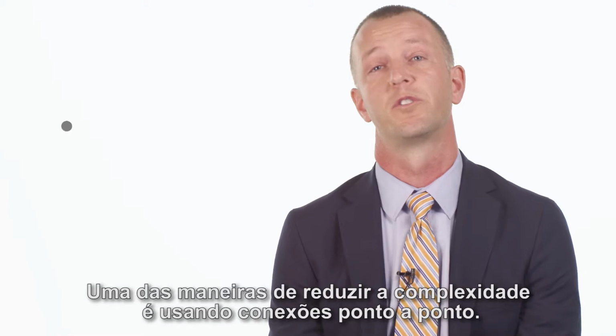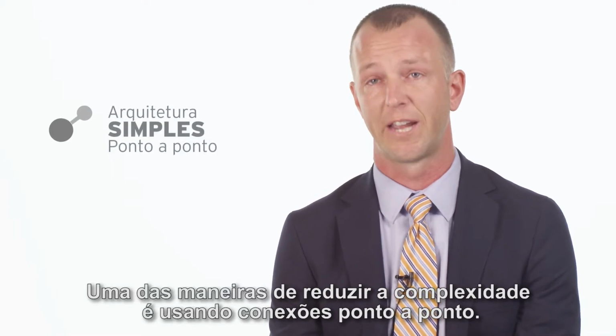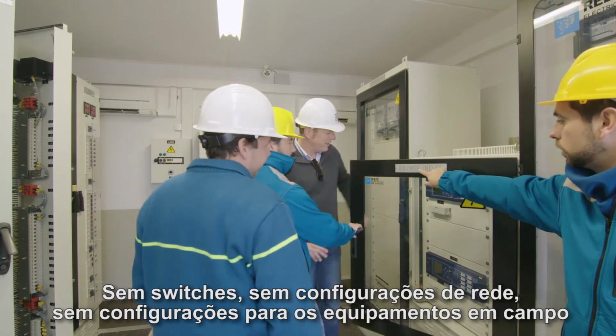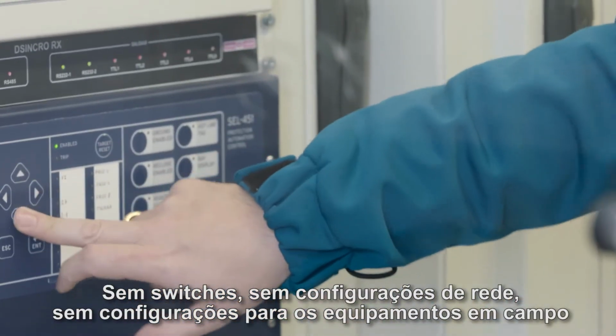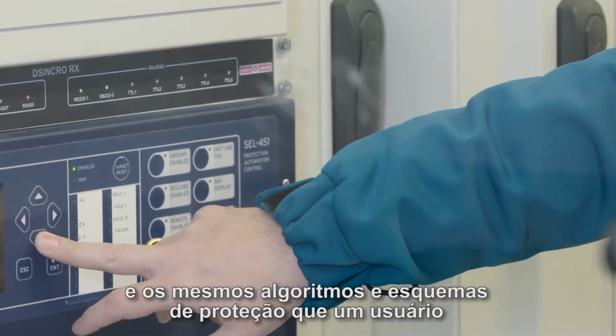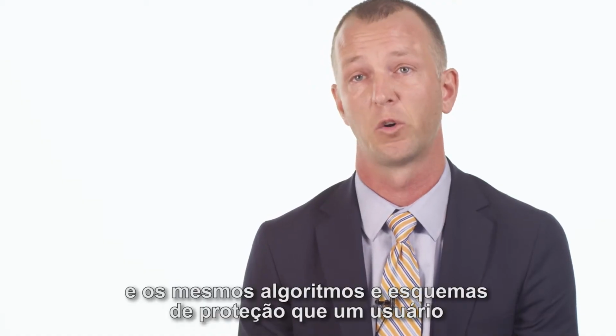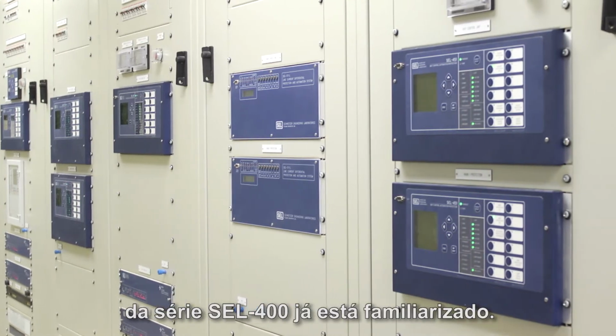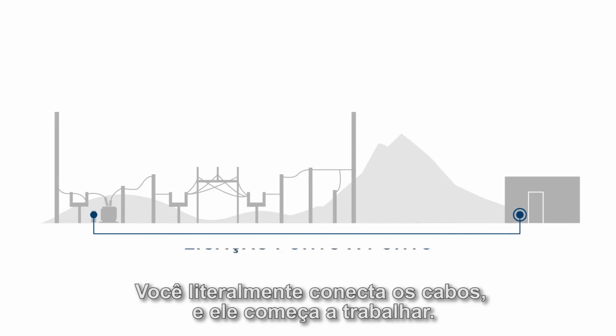One of the ways we reduce complexity is by using point-to-point connections: no switches, zero network configurations, no settings for the field devices, and the same protection algorithms and schemes that a user of a 400 series is already familiar with. You literally plug in the cables and it begins working.